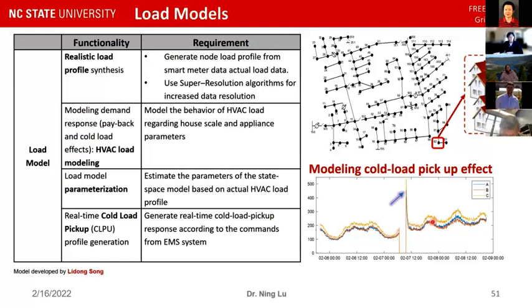We model this not just for normal operation but also for microgrid conditions, for example if I only supply one part of the feeder and then after 3 hours, when the sun is out, I pick these loads back up. In the past, people didn't consider how much load you need to pick up, because if a section is offline for 2 hours, the load you initially pick up is much higher than the original value. This is something unique that we considered.